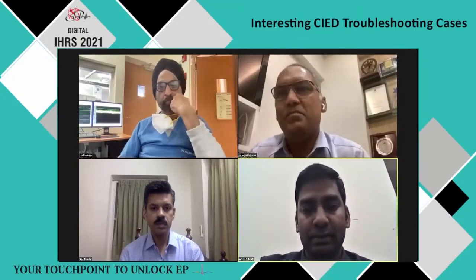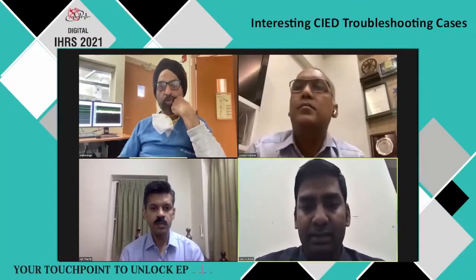Yes, sir. Actually, it's very, very low. Sensitivity of this phenomenon is very low. Actually, more sensitive is when you put in the lead and you see PVCs. That is very common when you put it on the septum. And then if you see a notched PVC, that is the time to progress. Instead of pacing, you could just straight away go in progress. If you don't see a Q notch in V1 with the initial PVC... Initial PVCs are much more common than once you have gone into the muscle and are now entering the LV septum. Those PVCs are rare. So the sensitivity of this test is extremely low. Yes, sir.